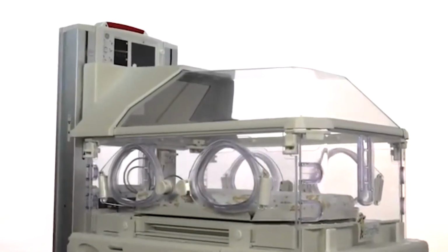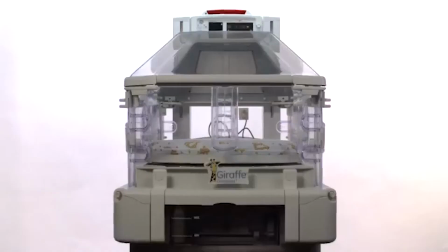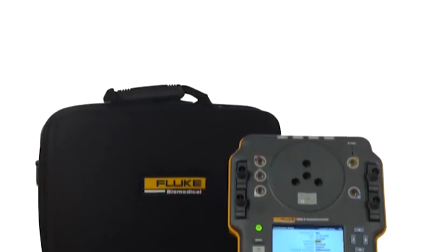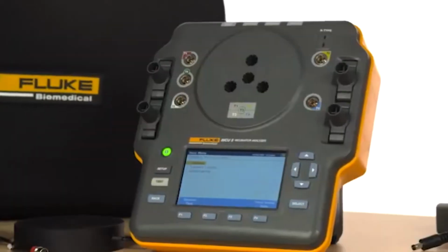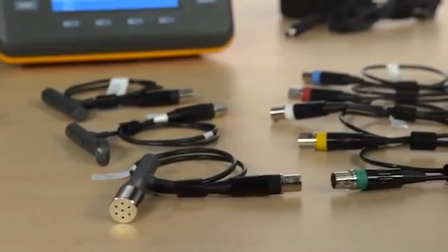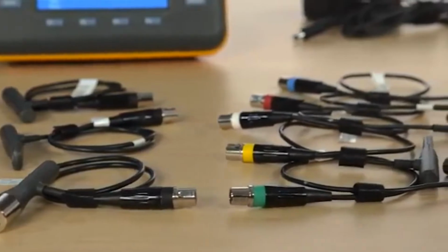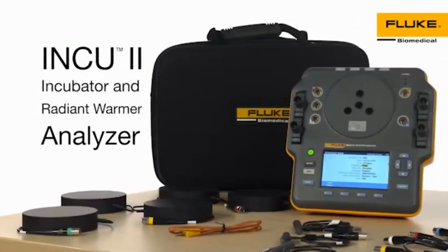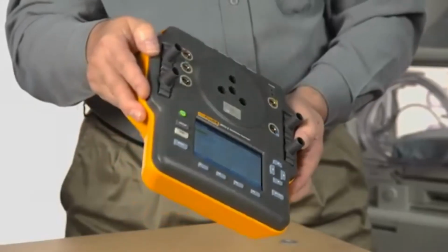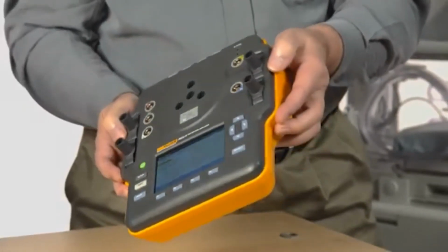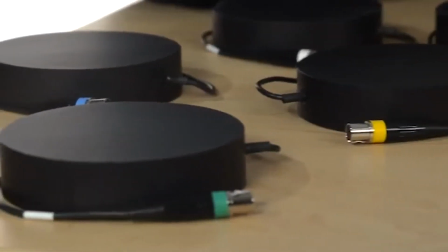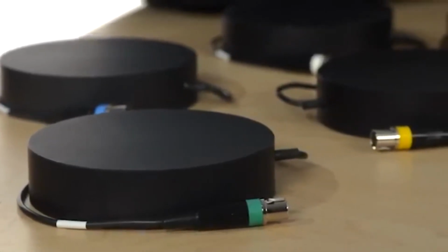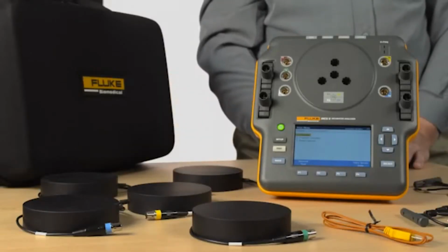Your smallest patients can be your most vulnerable, which is why it's essential you regularly test the performance and safety of your facility's neonatal incubators and radiant warmers. Fluke Biomedical would like to introduce you to the INCU2 Infant Incubator and Radiant Warmer Analyzer. The INCU2 is the only all-in-one portable and easy-to-use analyzer that complies with IEC 60601-2-19, 2-20, and 2-21 standards. You'll quickly notice its size, just 3 pounds, including the sensors for testing incubators. The pucks for testing radiant warmers come in their own case and weigh less than 9 pounds to comply with standards. Nevertheless, the INCU2 is the most compact, portable, and easy-to-carry analyzer of its kind on the market today.